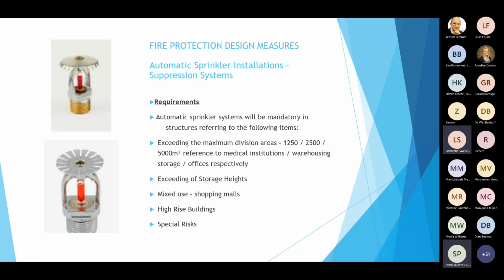Versus a category 2 system, which refers to lower risk with much less sprinkler density, and different pipe sizes compared to category 4. It all relates to the type of design and requirements, which at the end of the day comes down to budget costs, with bigger pump sets, bigger tanks, or smaller piping. Sprinkler design is much more in depth and difficult than simply saying, let's install a sprinkler system.